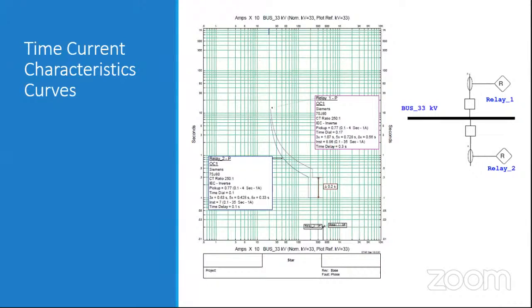You can see here in this time-current characteristics curve that for the 33 kV bus, relay 2, which is the downstream relay, should operate first. If it fails to operate, then relay 1 will operate after a certain time margin of 200 milliseconds. You can see the relay 2 curve operating at 0.1 seconds for instantaneous protection.